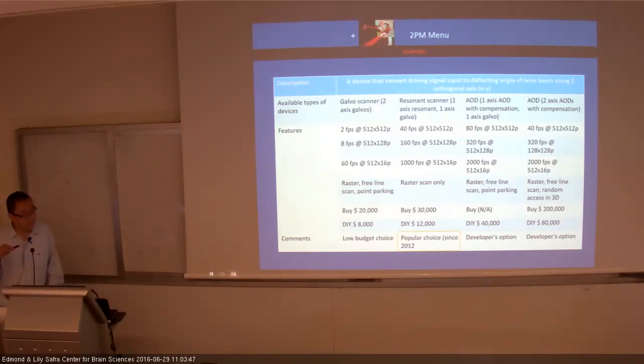A galvo scanner is a mirror that is electrically driven by an electromagnet. That is the deflection angle. Let's say the mirror's angle is proportional to the amount of current flowing through this driver. So that is very good because then you have a linear drive. You give a current. 1 ampere is at 10 degrees, then 2 ampere is at 20 degrees. Very simple and straightforward. This is used in the early microscope systems and also a lot now actually. The advantage is that instead of driving it sequentially like this, you could drive in any arbitrary line, or like zigzag, or anyway.